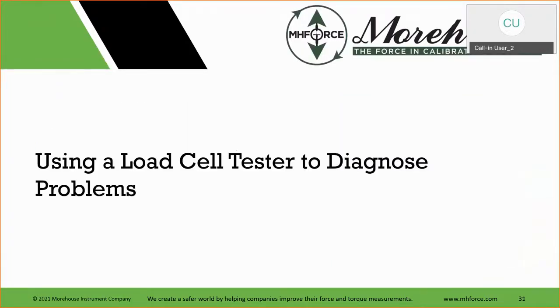So, we've talked a lot about a load cell tester. It's a tool, we resell them. They're branded, and they're made in Israel by a company, and when we first sold them, we just loved them because they save a tremendous amount of time. It's a product that's under $1,000, and if you've been in a lab and you've had bad load cells, or you've been concerned with them, you start asking, what would it cost if a tech overloaded a load cell and we waited a full year till we really found out? We know the output shifted. And then we suspect it shifted, and then the calibration laboratory confirms it. What would that really cost? What type of recall would happen? Would a recall happen? Would it not happen? Would it be out of tolerance to your specifications? These are all questions internally everybody has to ask.